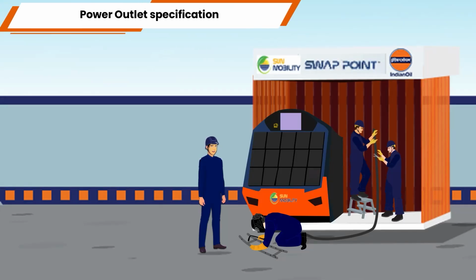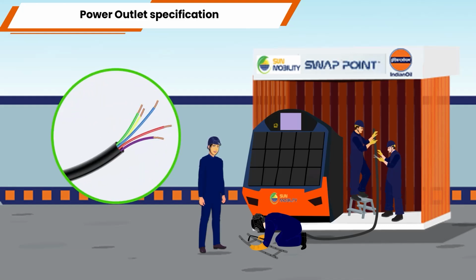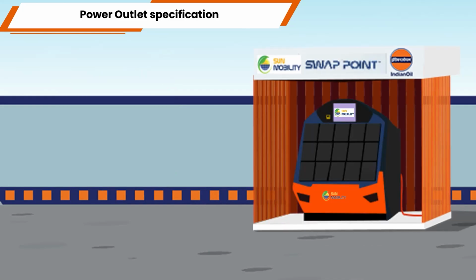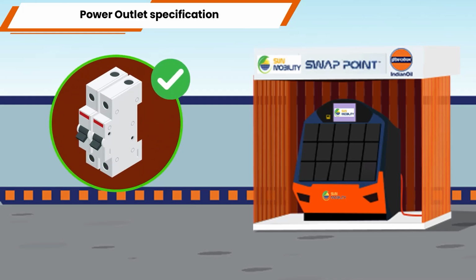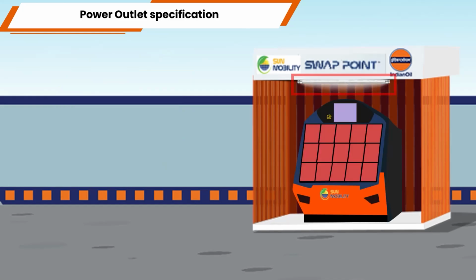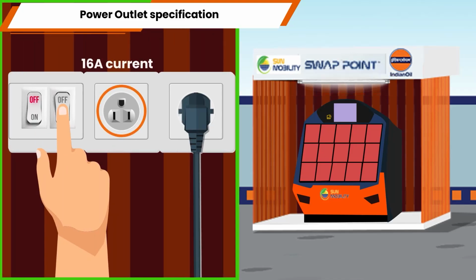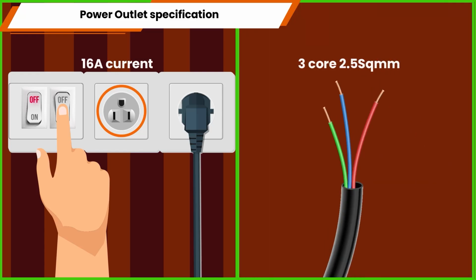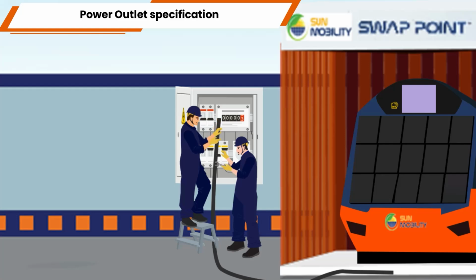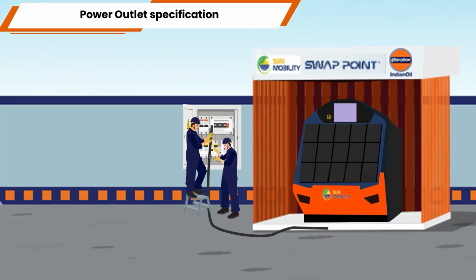Power outlet specification. The QIS requires a 16 square millimeter 5-core copper flexible cable of length 2 meters at the site for installation. There needs to be an MCB at the electrical outlet for primary protection at the inlet of the QIS. QIS provides power to all its internal components and can also power site lighting and electrical over a metered outlet. This outlet can support up to 16 ampere continuous current draw. The cable may be 3-core 2.5 square millimeter rated for 16 ampere current. The electrical panel should not create any hindrance for deployment and service activities.